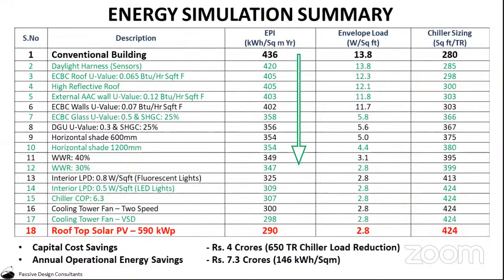From 436, we can bring it down to almost 290, which means the project would actually save almost 146 kilowatt hour per square meter, which translates for a 50,000 square meter building to 7.3 crores annually. So this is not only energy savings, this is actually cost savings also for the project, for the building. Imagine if we do this kind of value engineering for a project, if we optimize our building designs, if we make our building energy efficient, how much we can actually save at an entire Punjab state level or at a country level. The kind of carbon emissions that will be reduced will be enormous.